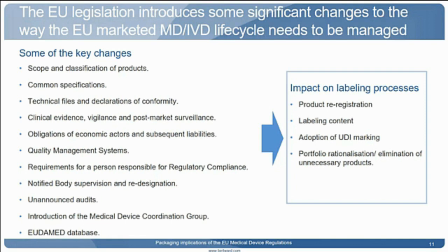We've then got common specifications, technical files, clinical evidence, vigilance, etc. There are a lot more requirements for the pre-marketing testing and post-marketing assessment of products. So companies are going to find that when they come to re-register their products for the new legislation, they're going to have to likely provide far more information than they provided in the past. This is going to make the registration processes more onerous, and time will need to be built into re-registration processes to be able to do that.